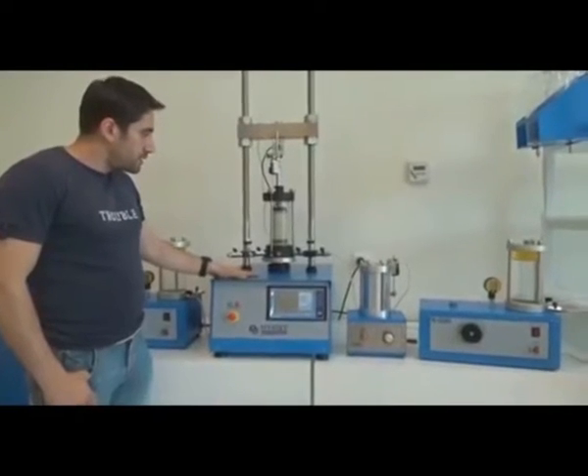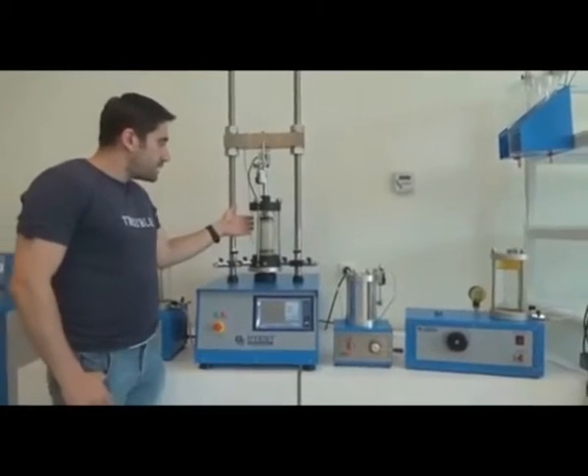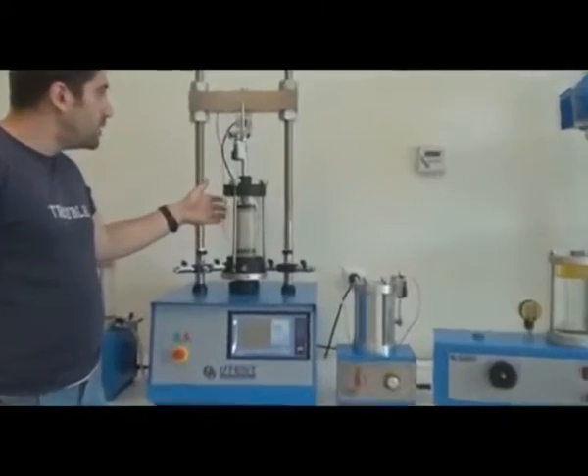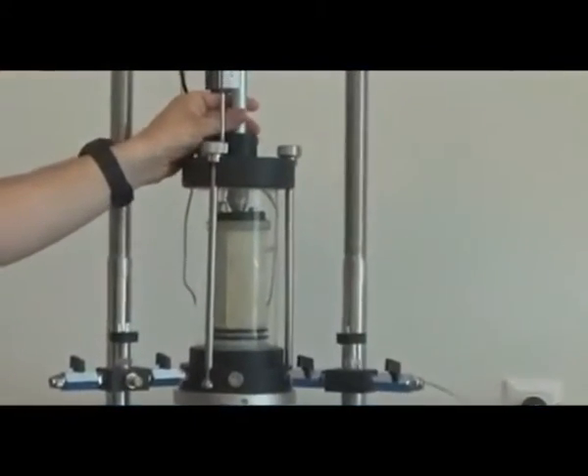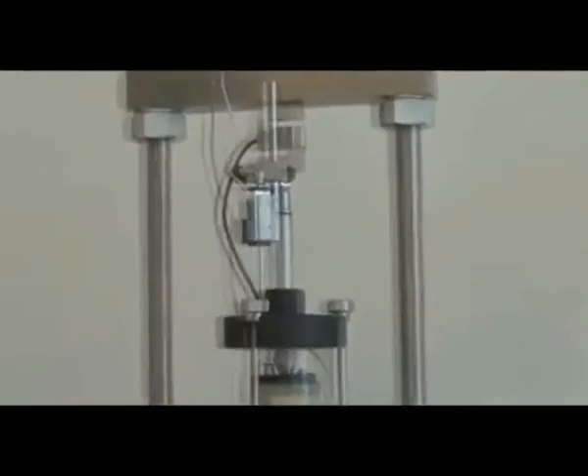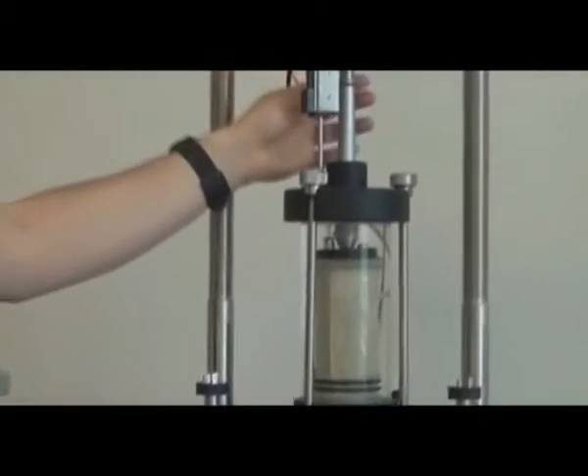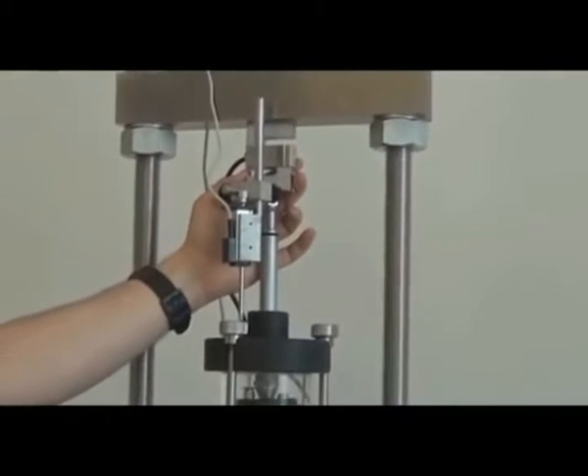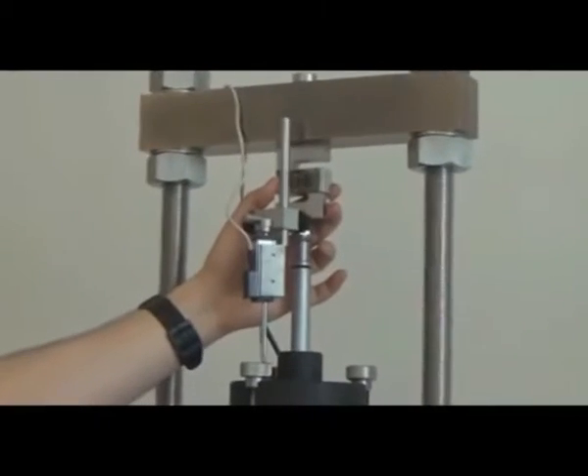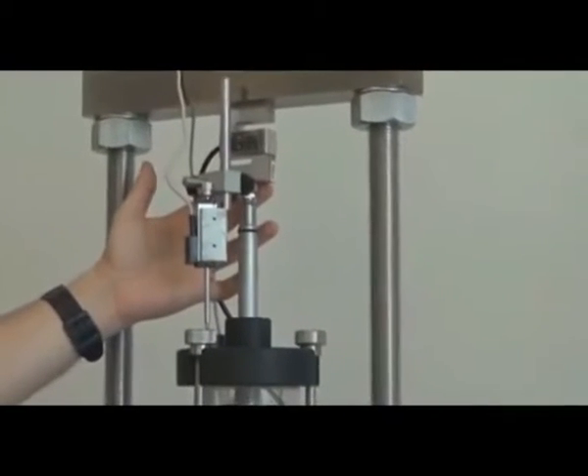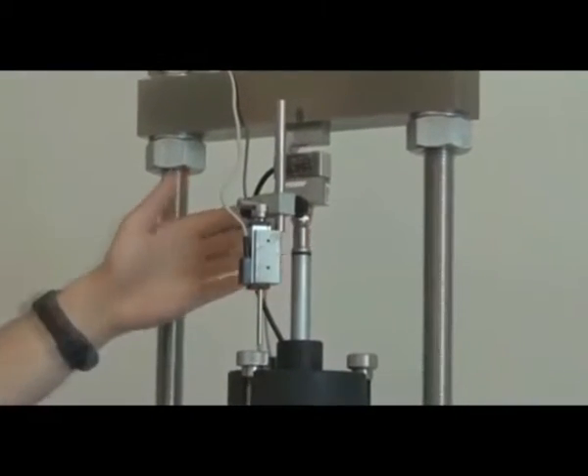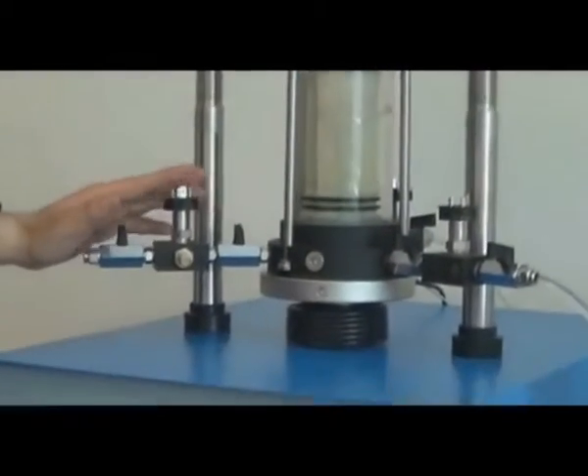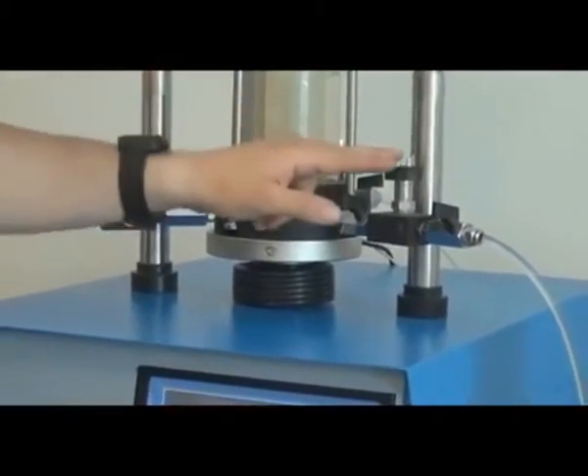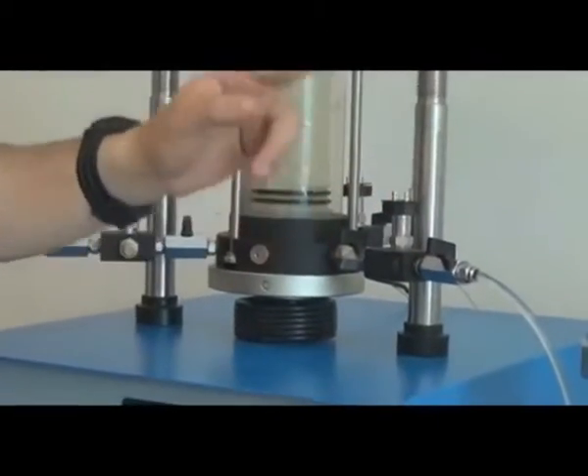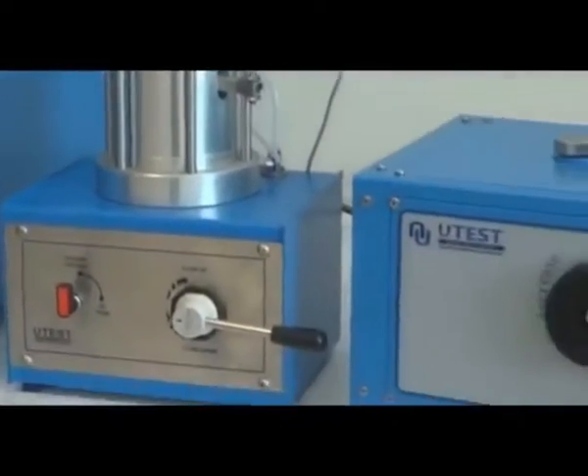And this is the multiplex machine, which has the triaxial cell mounted on it. The triaxial cell has a piston to transmit the force to the specimen vertically. And this piston is connected to an S-type load cell, which has 500 kg of load capacity. The triaxial cell has 3 pressure transducers mounted on it, and they will be connected to the data logger afterwards.